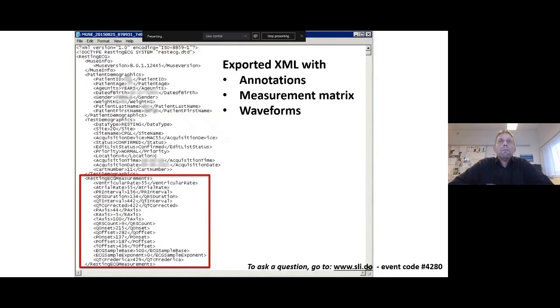But I think the most important format that we use in our research is the XML format that we can export from MUSE because here we have everything in one single file. We have the annotations of fiducial points so we can know where all the intervals are measured on the ECG waveforms. We have the ECG measurements in the measurement matrix. I've highlighted some of them here in the red rectangle. More importantly, we also have access to the raw ECG waveforms because they are included in the export of the XML files.